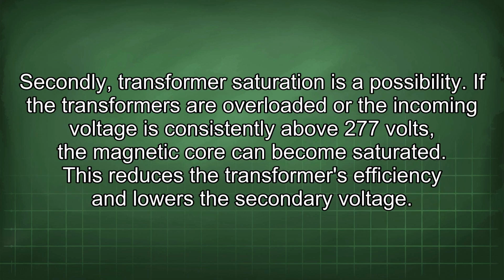Secondly, transformer saturation is a possibility. If the transformers are overloaded or the incoming voltage is consistently above 277 volts, the magnetic core can become saturated. This reduces the transformer's efficiency and lowers the secondary voltage.